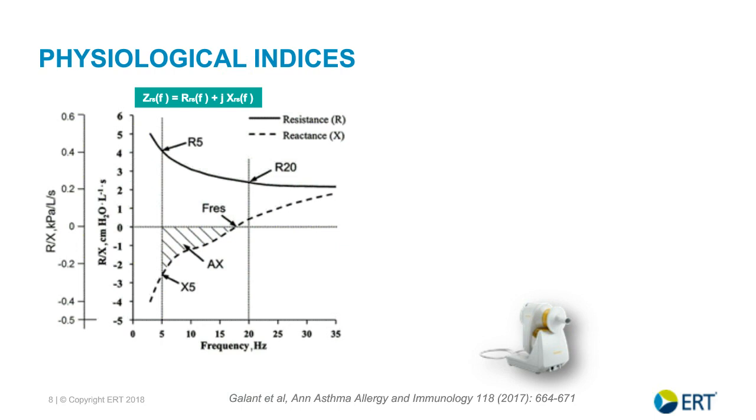So here you have a patient that's breathing. The flow related to breathing is subtracted from the pressure oscillation, and what you measure at the mouth is the response of the respiratory system. So that's the airway gas column, the lungs, the lung parenchyma, the chest wall, in response to that oscillation. You measure pressure and flow over time. Now, the pressure divided by the flow at any particular point in time gives you something called the impedance.